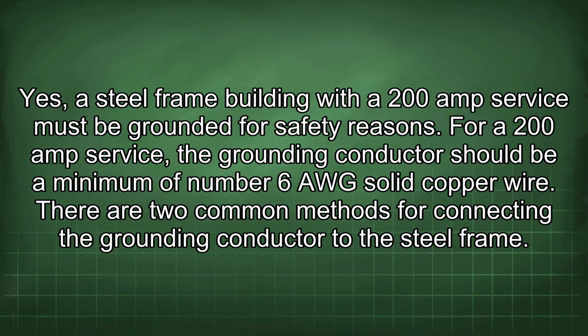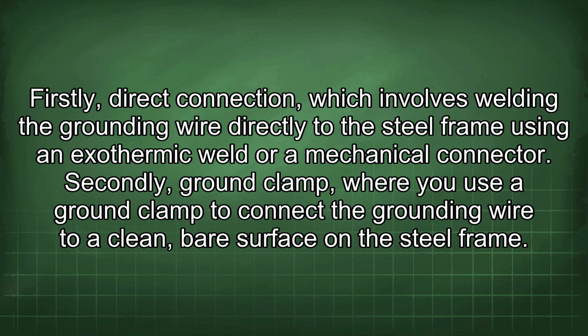Yes, a steel frame building with a 200 amp service must be grounded for safety reasons. For a 200 amp service, the grounding conductor should be a minimum of number 6 AWG solid copper wire. There are two common methods for connecting the grounding conductor to the steel frame. Firstly, direct connection, which involves welding the grounding wire directly to the steel frame using an exothermic weld or a mechanical connector. Secondly, ground clamp, where you use a ground clamp to connect the grounding wire to a clean, bare surface on the steel frame.